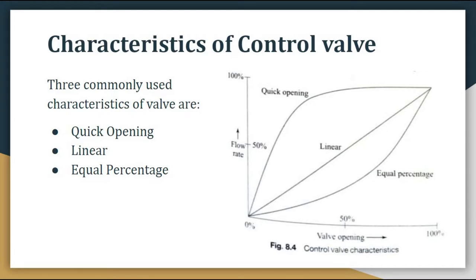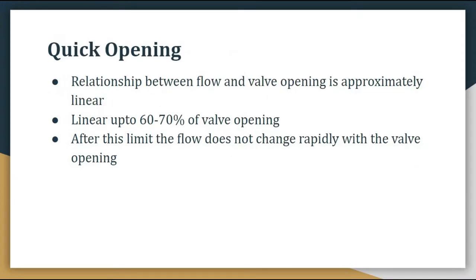There are three commonly used characteristics of control valve which are: quick opening, linear, and equal percentage. This is the graph you can see, which we will be referring to while explaining these three characteristics of control valve. First we will discuss quick opening characteristic. In quick opening, the relationship between the flow and the valve opening is approximately linear up to 60 to 70 percent of the valve opening.